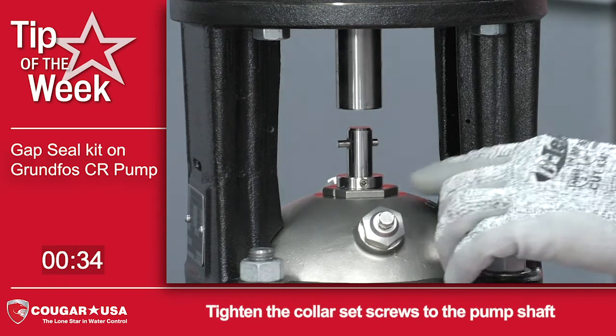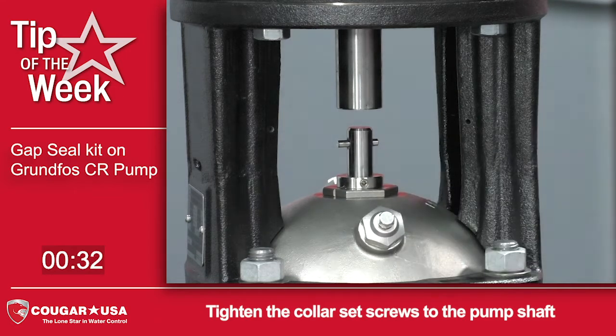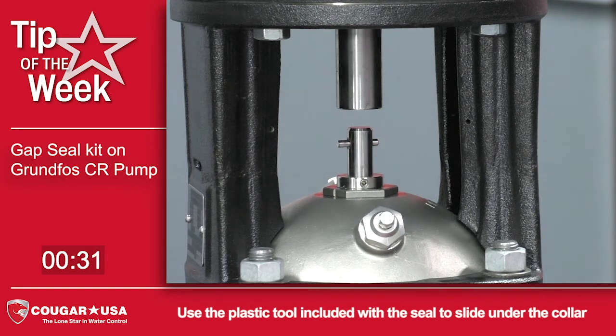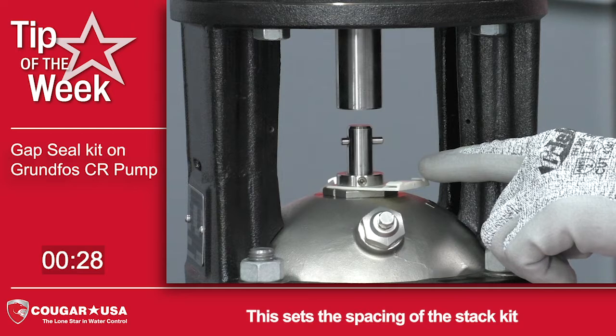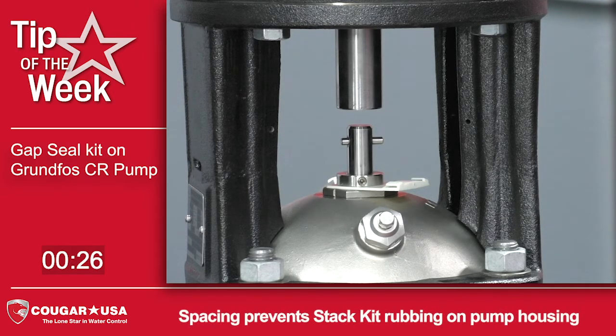After the seal kit has been screwed in, you tighten the collar set screws to the pump shaft. You want to use the plastic tool that comes with the seal kit, and lift and slide that underneath the collar so it lifts up the stack kit. This is going to prevent the stack kit from rubbing on the pump housing.